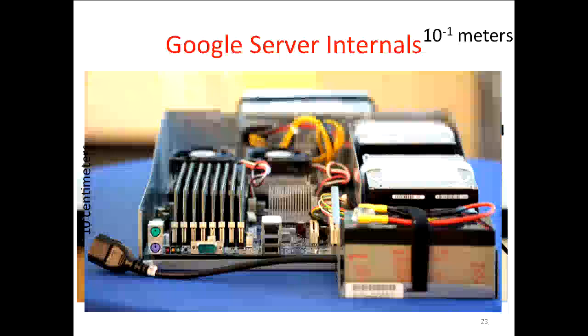And data centers have amazing power backups, right? Because they're 10 megawatt installations. They have to keep running, even if there's a power outage. So where do you get 10 megawatts of power from when the lights go out, when the mains goes out? Well, it turns out that these big data centers actually have several cascades of backup. So they have batteries for a very short period of time, and then they have massive diesel generators. And these things are about the length from here to that wall. Big things. And each one can generate a couple megawatts of power.